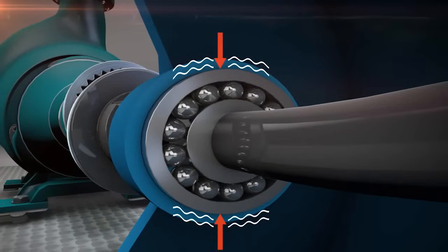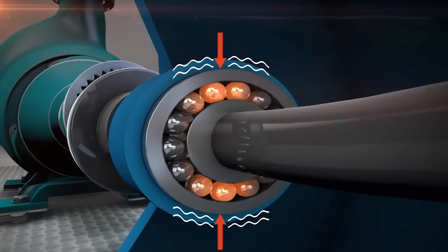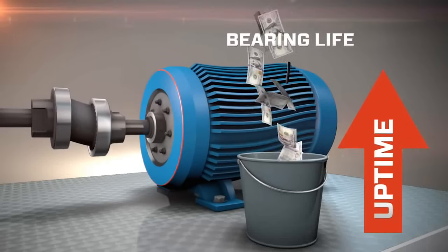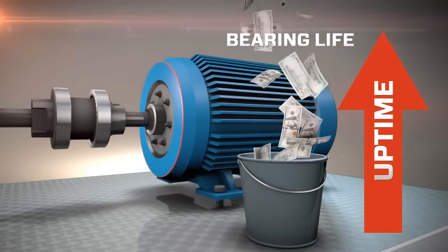it pushes on the bearing, causing out-of-roundness. These forces on the bearings cause them to wear unevenly and fail prematurely. So fixing a soft foot condition will always increase the life of the bearings and the efficiency of the machine.